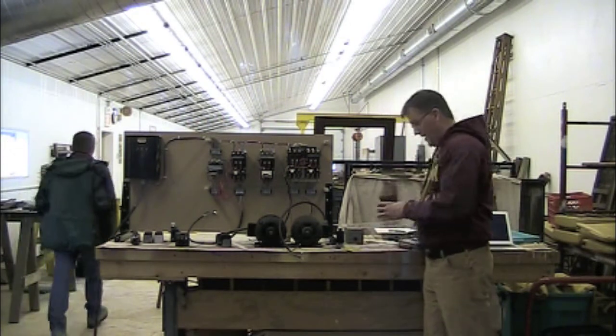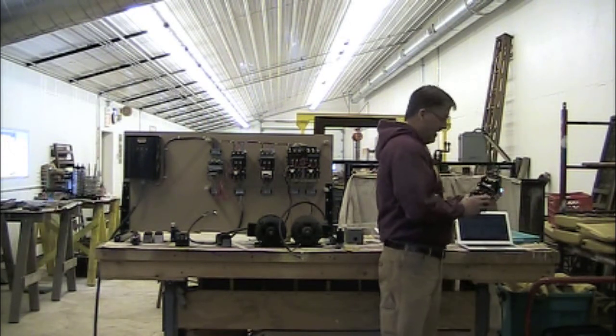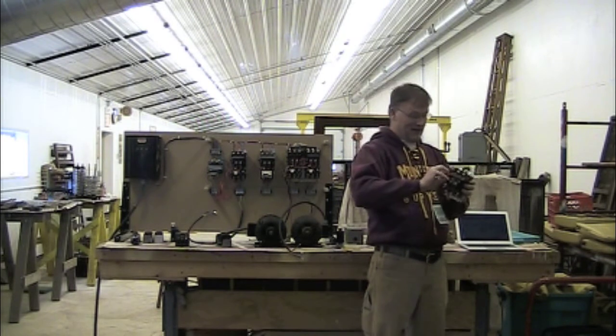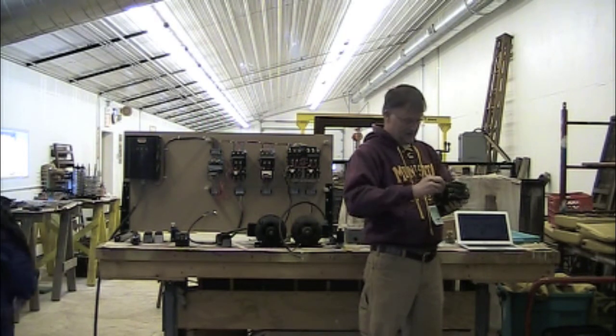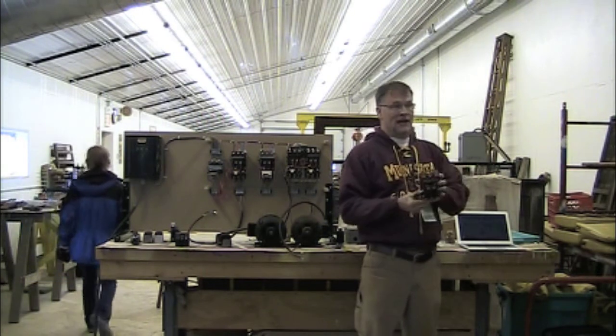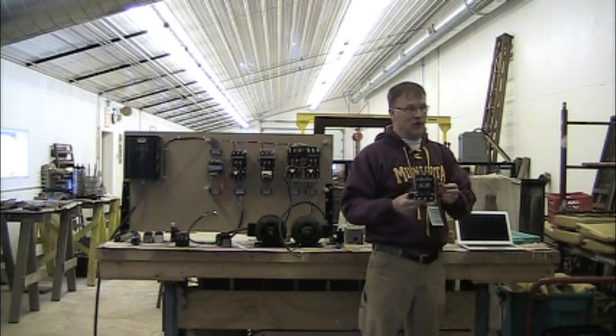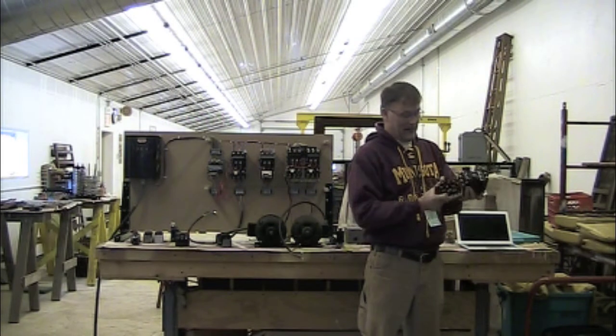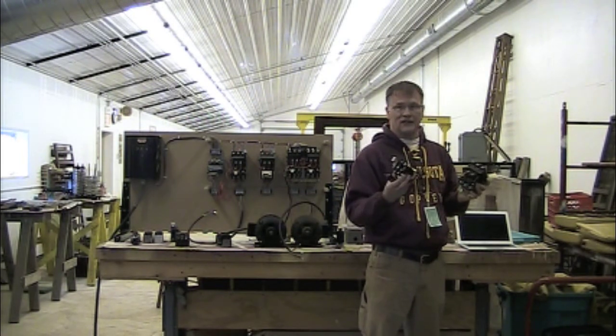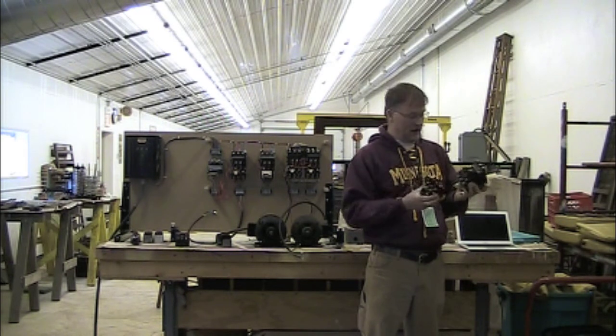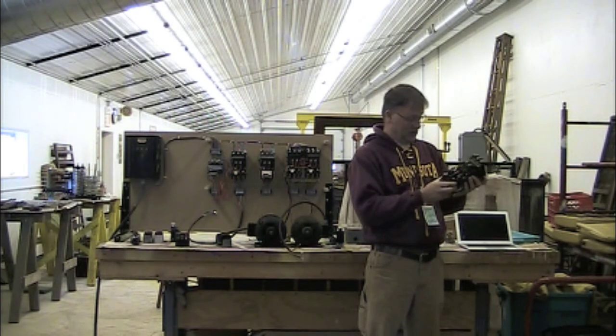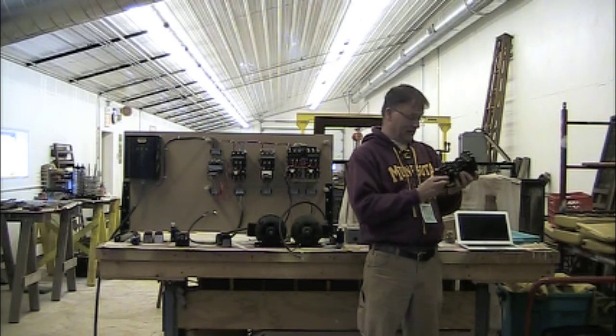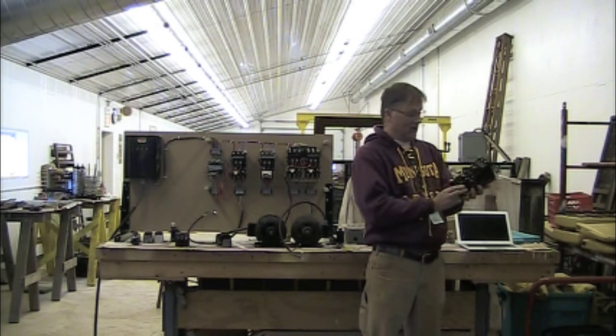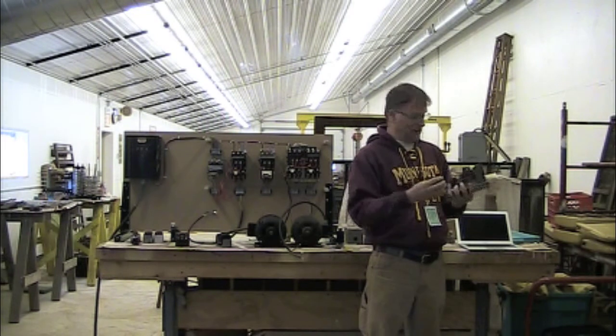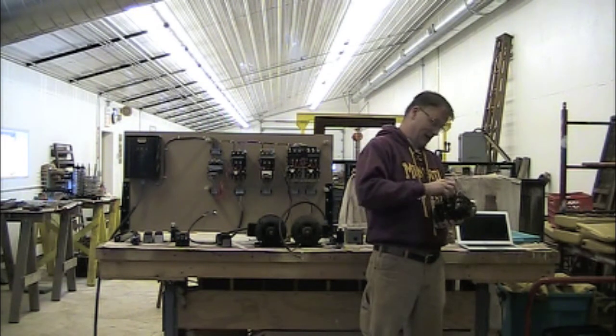So a starter is basically composed of a magnetic contactor. I can get this piece off now. The contactor piece. So this is controlling the voltage to the motor, and that's coupled to an overload block. This is the element that senses what the current draw on the motor. So that's just on the Allen Bradleys. These are just composite devices. That's just going on the bottom. And then it has a set of auxiliary contacts that are used to control the control circuit.